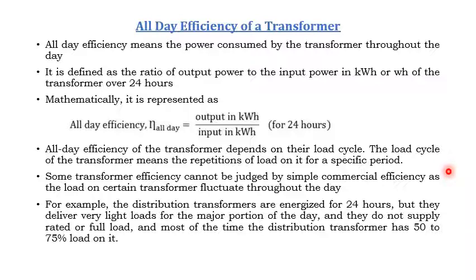You may obtain 100 kilowatt continuously for 2 hours, or for 1 hour. At the first hour you can get 100 kilowatt, then in the second hour 200 kilowatt, then again 100 kilowatt. That means the load is obtained repeatedly. In that case it is very difficult to calculate the efficiency of that particular transformer, so the all day efficiency is calculated.